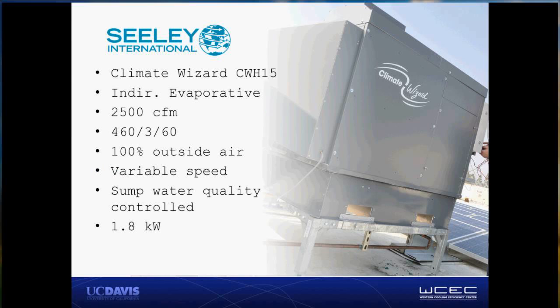The system is also 100% outside air and also variable speed, so it has many of the same part load capabilities as the Coolerado. This system uses a sump and recirculates water across the heat exchanger, and the sump water quality is controlled using a conductivity sensor, and their onboard controller makes a decision about when to bleed or dump water from that sump, and then the level of the sump is maintained using a level sensor.